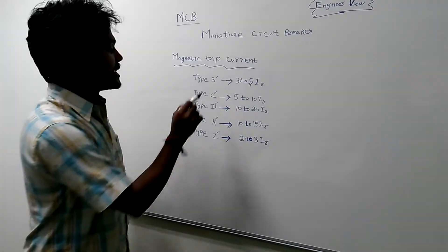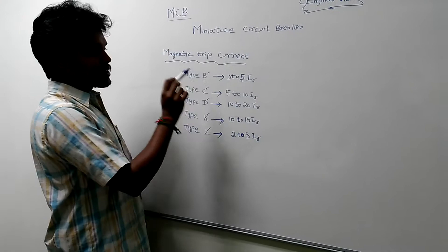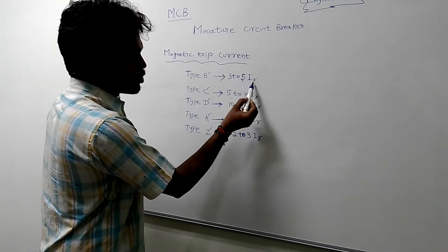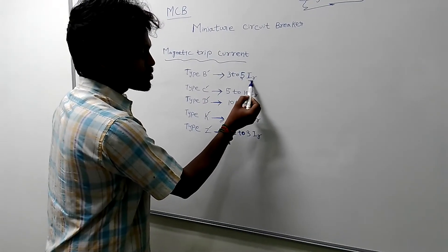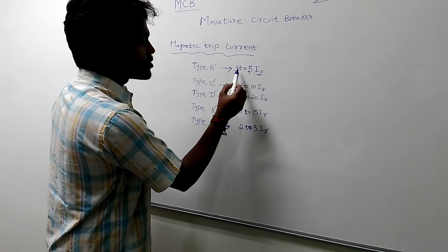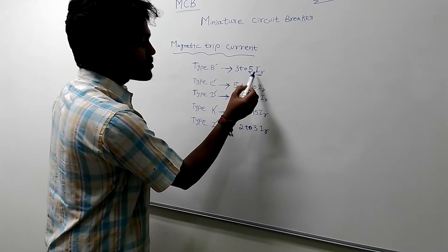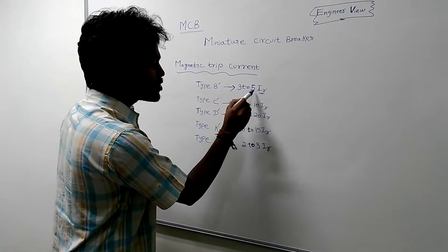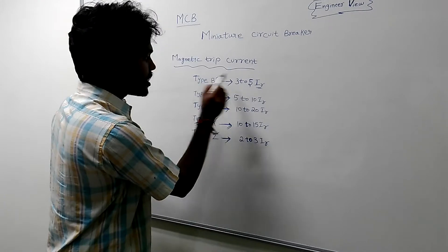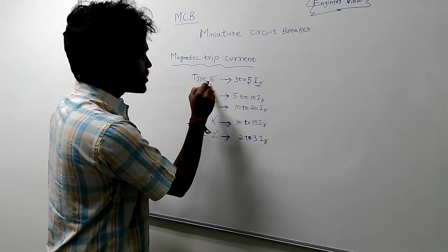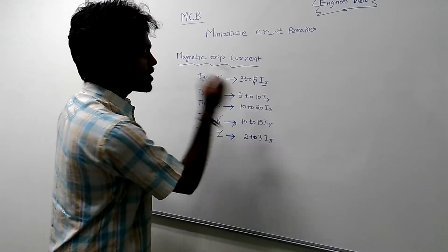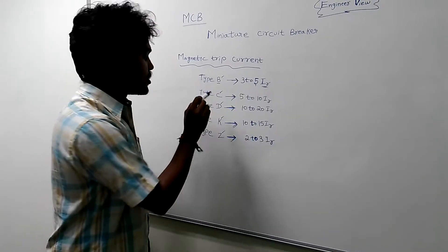If you want to talk about MCB Type B, it trips at 3 to 5 times the full load current. The rated current is the full load current, so the tripping range is 3 to 5 times of the rated current — that is the tripping capacity for Type B.